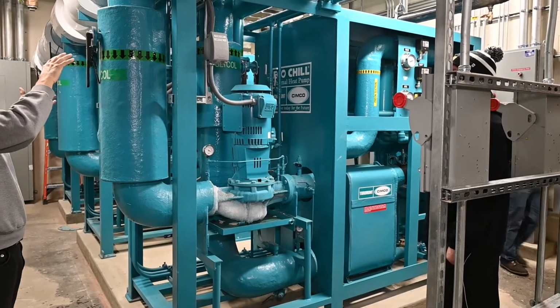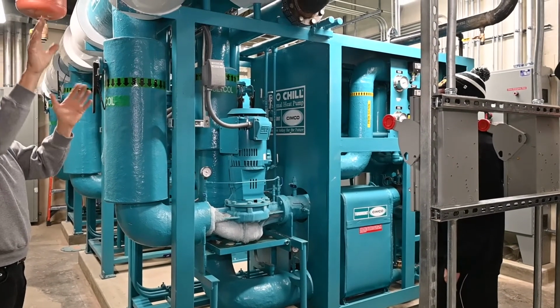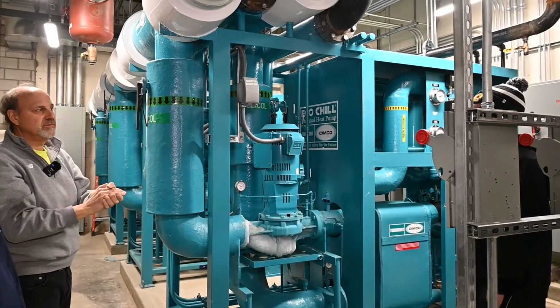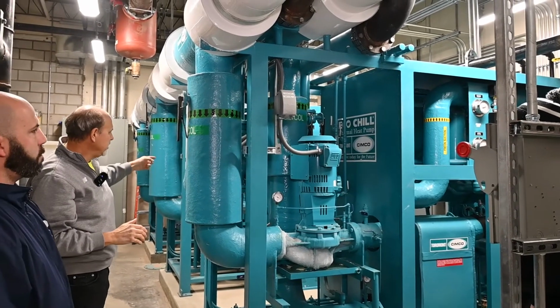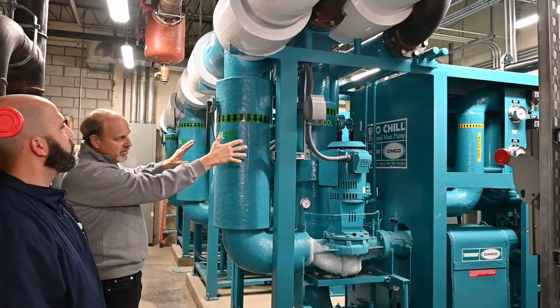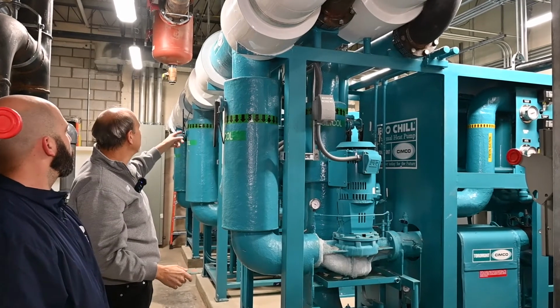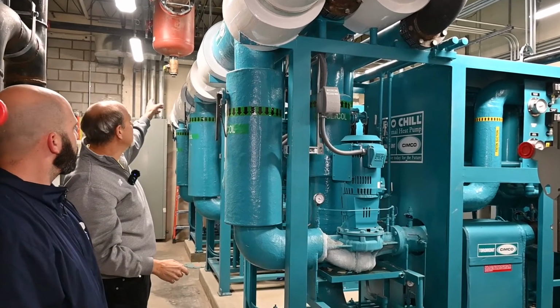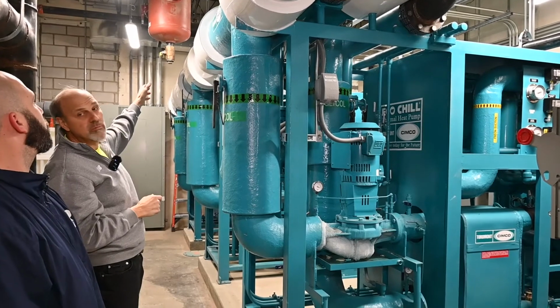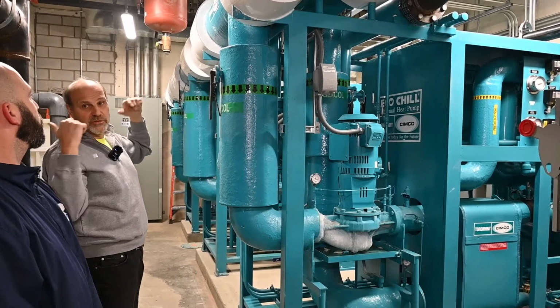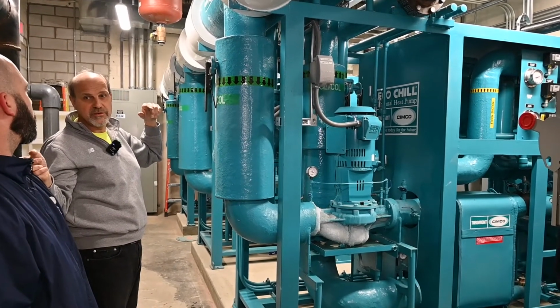And the cooling system loop is just going to have glycol going out to the rink to maintain the cold. To cool these compressors, and Carl will go over the chiller arrangement in a minute, there's a 6-inch warm glycol loop that goes out to your cooling towers or to this heat exchanger behind us.